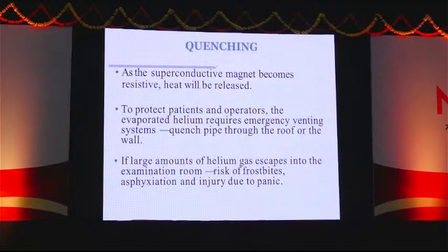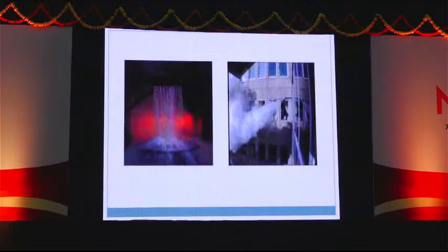As a superconductive magnet becomes resistive, heat will be released, and to protect patients and operators, the evaporated helium requires an emergency venting system, a quench pipe through the roof or the wall. So this is the image showing the helium quenching throughout the building.